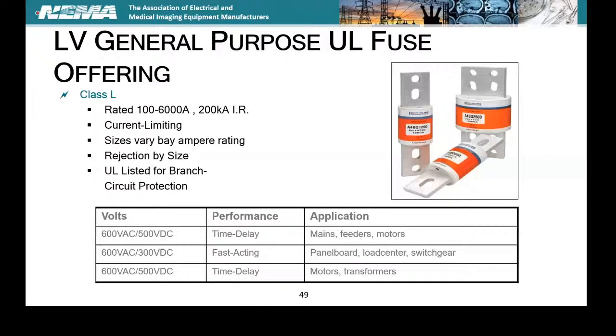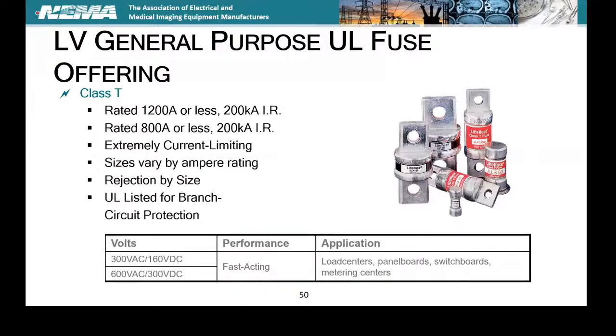They've got time delay and fast acting for panel boards. Motor. Look where your time delay is. Motors and transformers, inrush currents. So those are your big boys, and they bolt onto the bus basically for the most part. Your Class T. T is for tiny. T for tiny. You get up to 1,200 amps, but they are much smaller than the Class L, which is large. So your Class T's are your smaller fuses.